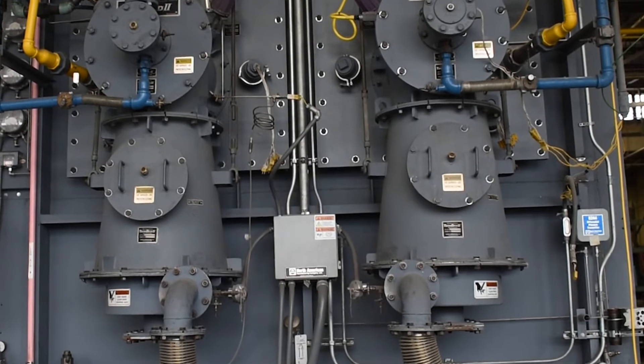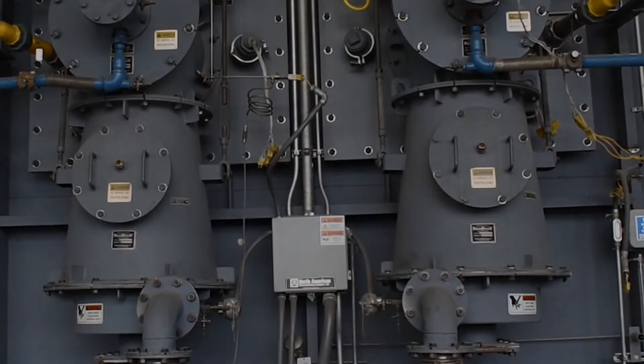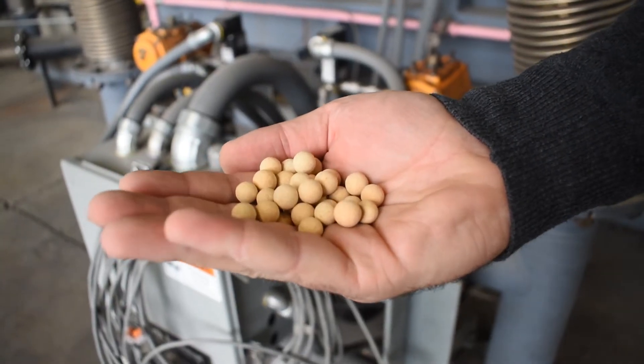Conversely, during the exhaust cycle, the burner transfers energy from the products of combustion in the furnace to its heat exchanger. Each burner has its own heat exchanger mounted directly below the burner head. The heat exchanger is composed of ceramic balls.